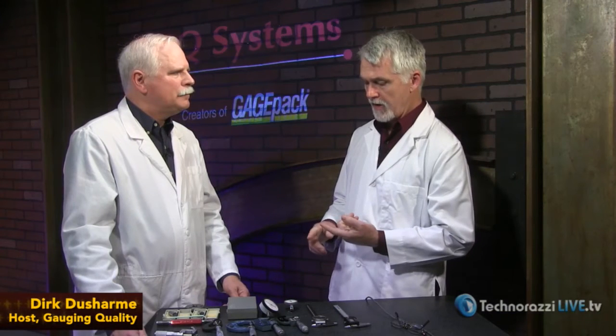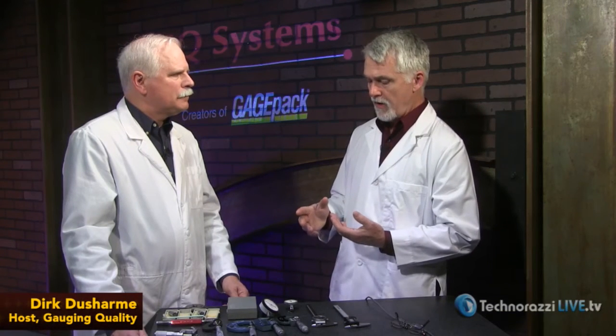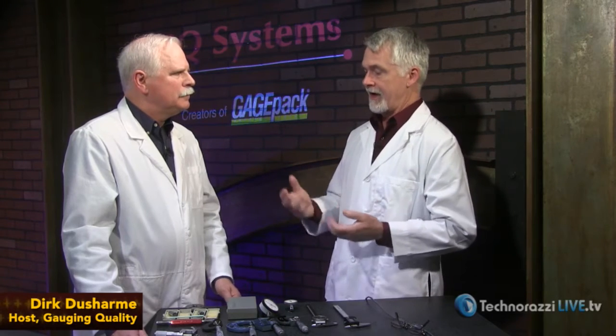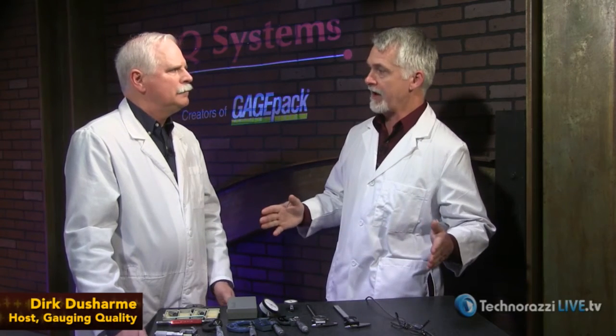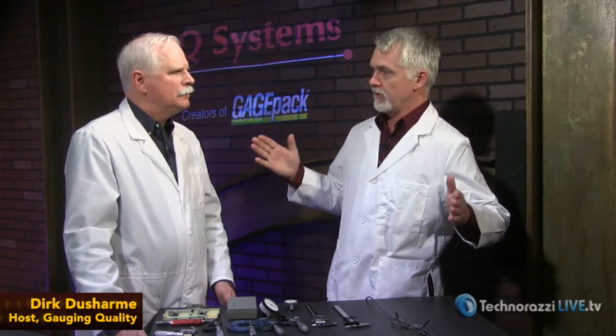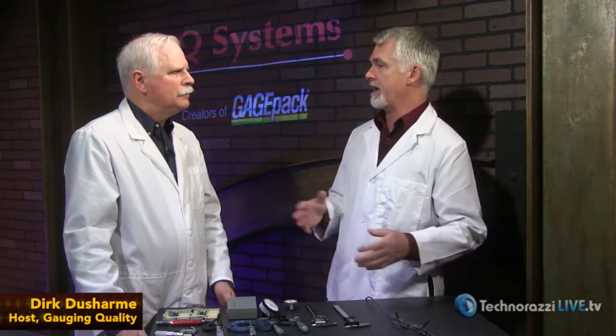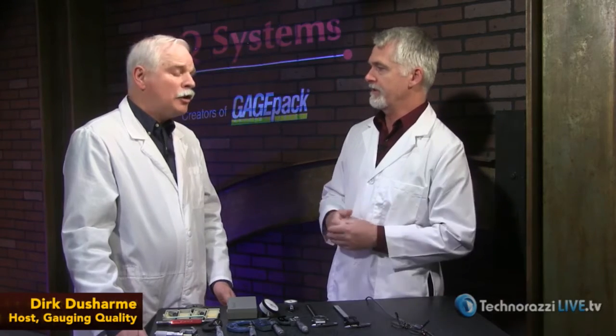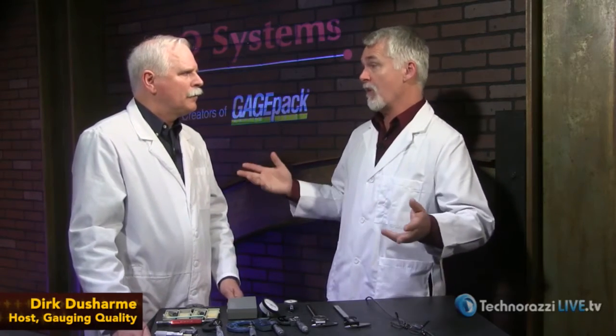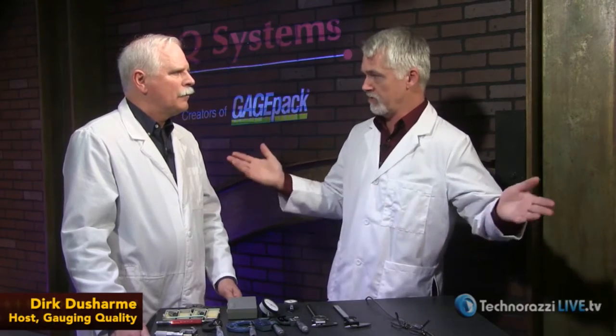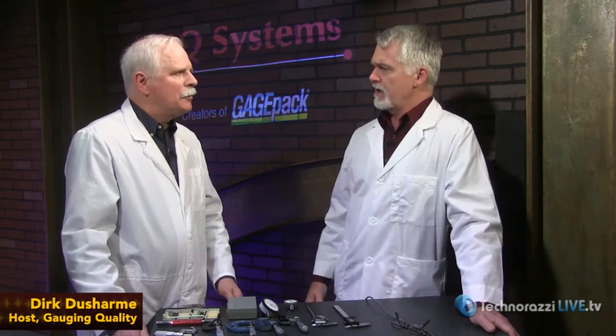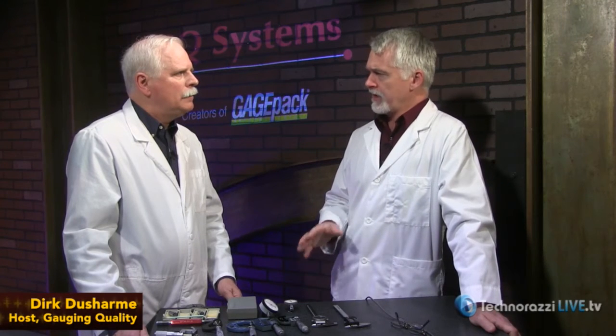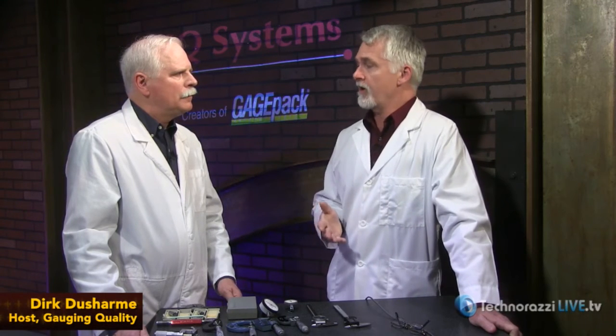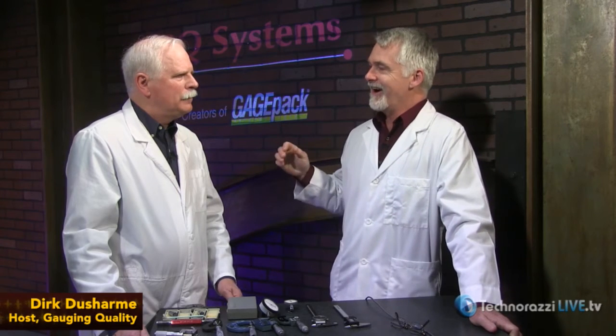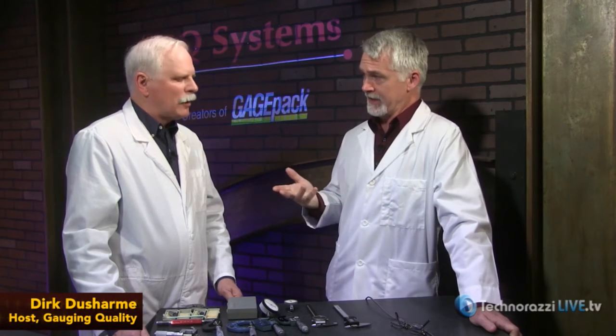Now, you mentioned earlier that one of the criteria is the accuracy that they're calibrating to. So, might a mobile lab specify that we use our mobile lab for calibrations within so much accuracy? It's a good point. But if you want more than that, well, you're going to have to send your equipment to our fixed lab or whatever. Because that would work with the larger tolerances. You could have more temperature variation without really seeing an impact.